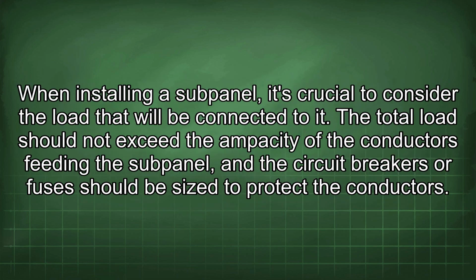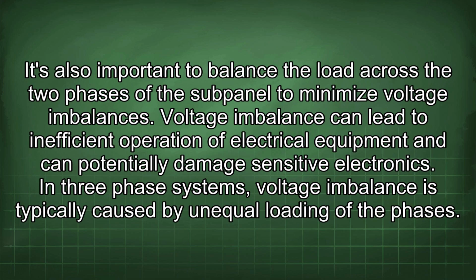When installing a subpanel, it's crucial to consider the load that will be connected to it. The total load should not exceed the ampacity of the conductors feeding the subpanel, and the circuit breakers or fuses should be sized to protect the conductors. It's also important to balance the load across the two phases of the subpanel to minimize voltage imbalances. Voltage imbalance can lead to inefficient operation of electrical equipment and can potentially damage sensitive electronics.